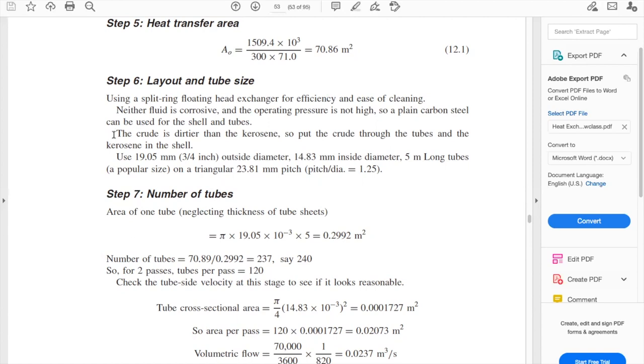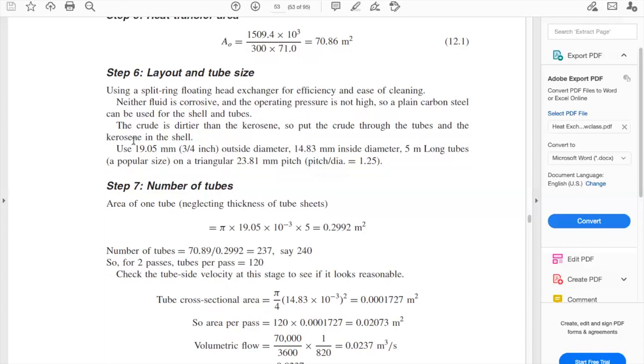We need to select the fluid routing. Neither fluid is corrosive and operating pressure is not high, so plain carbon steel can be used for the shell and tubes. Material selection depends on the fluids you are using. The crude is dirtier than the kerosene, so put the crude through the tubes and the kerosene in the shell. This agrees with the textbook recommendations on where to route each fluid.